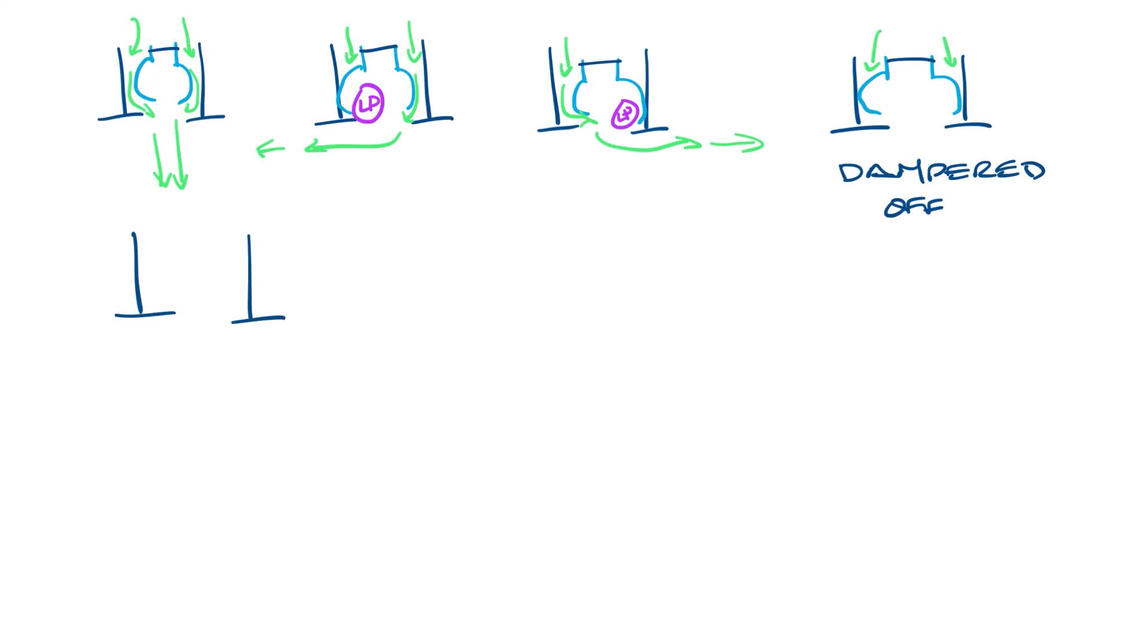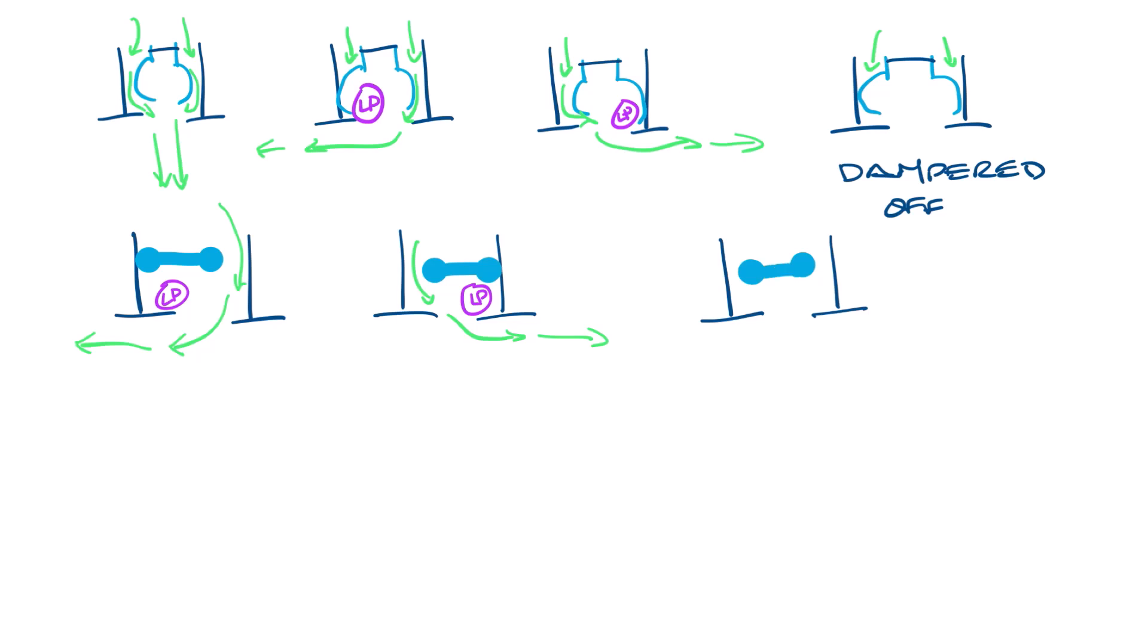And if we look at the dumbbell shape pattern controller, it slides side to side. So if you slide it all the way to one side, you get a low pressure zone in here and the air flows this way and goes across the ceiling. If you push it to the other side, your low pressure zone goes to the other side and the airflow will go in the other direction. And if you leave it in the middle, the airflow goes around both sides and straight down.